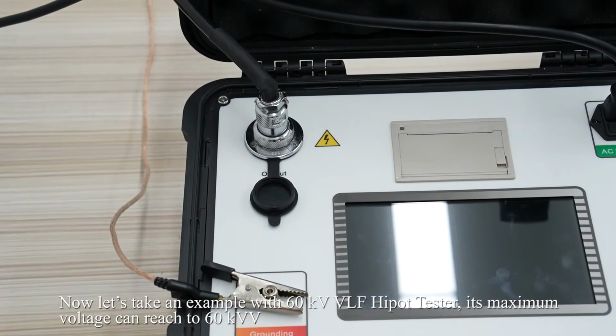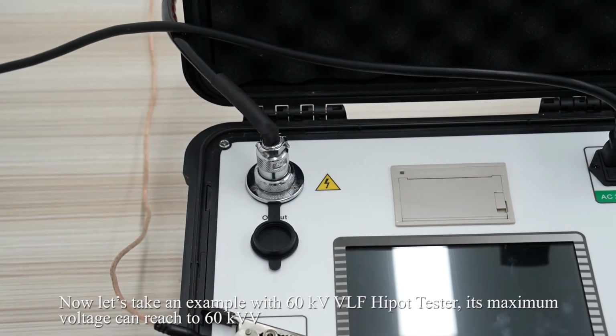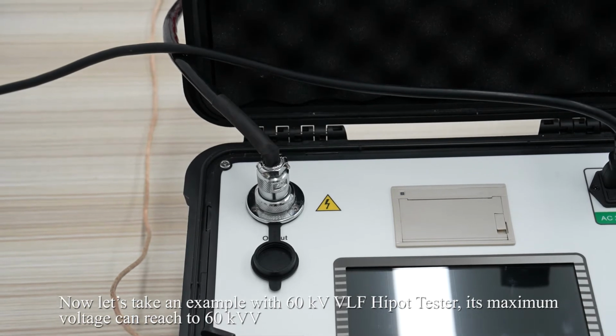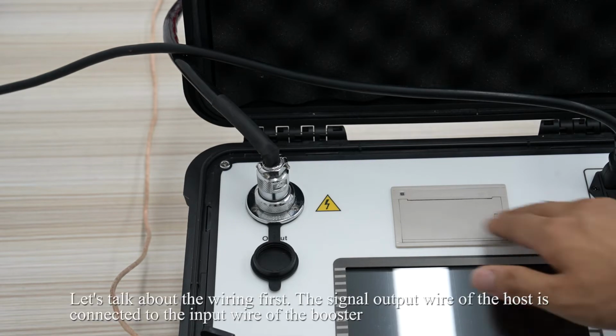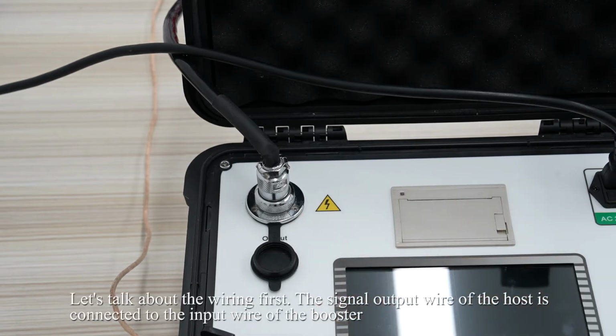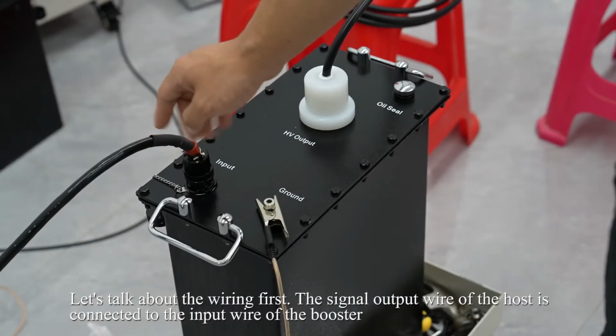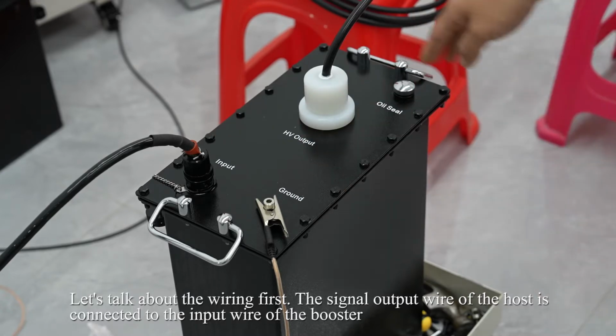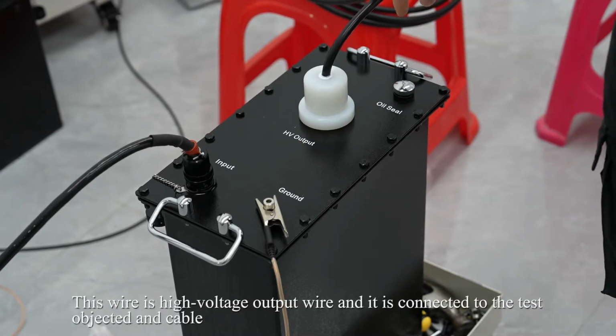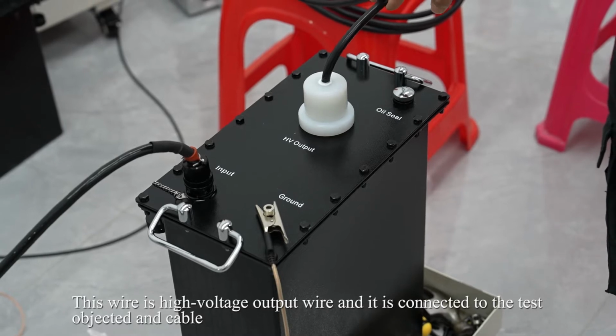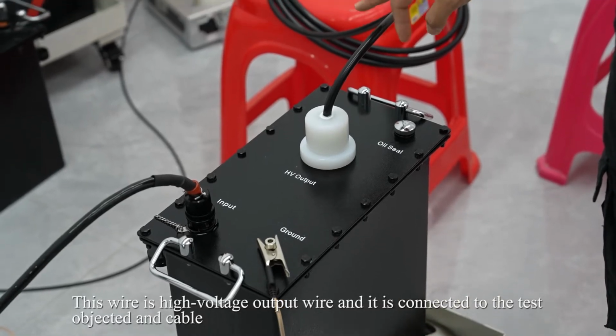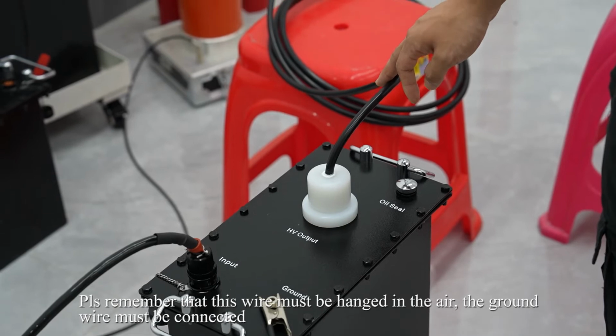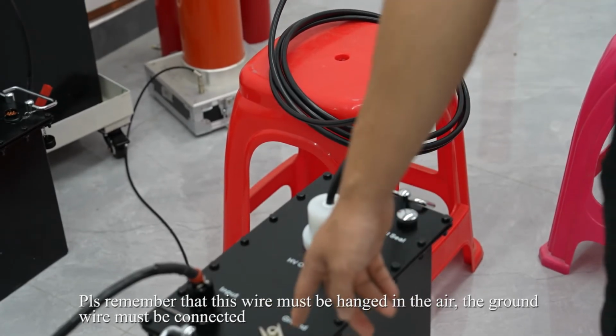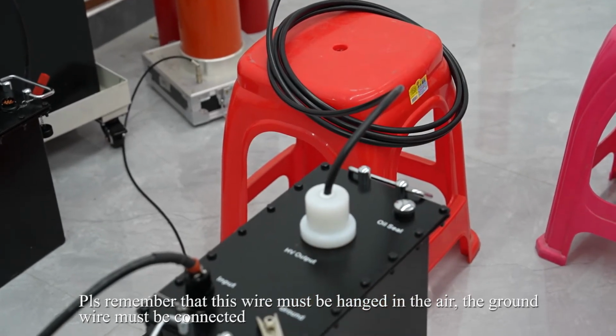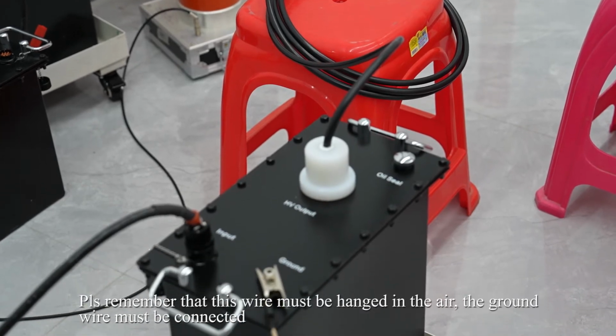Now let's take an example with a 60 kV VLF Hipot Test Set. Its maximum voltage can reach 60 kV. Let's talk about the wiring first. The signal output wire of the host is connected to the input wire of the booster. This wire is the high voltage output wire and is connected to the test object, our cable. Please remember that this wire must be held in the air. The ground wire must be connected.